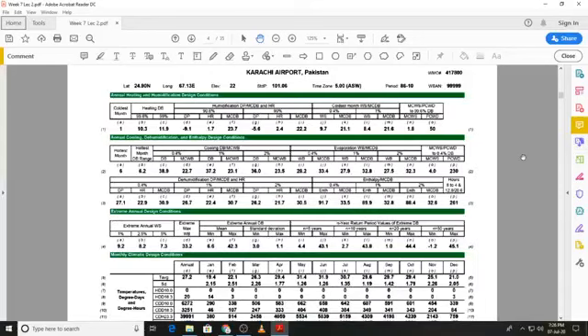You can now see a climatic data sheet for Karachi airport, and it has certain information on it. Of course, we have the latitude, longitude, elevation, standard pressure, the time zone, and the period over which the data has been collected, and based on that period they have developed this climatic data sheet. And there is an identification number for the weather station. Then for a person interested in air conditioning, you have the annual heating and humidification conditions and the annual cooling, dehumidification and enthalpy design conditions.